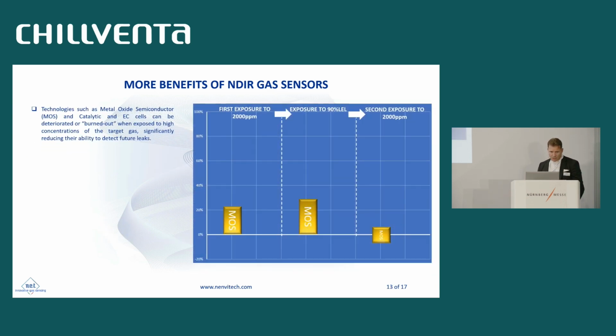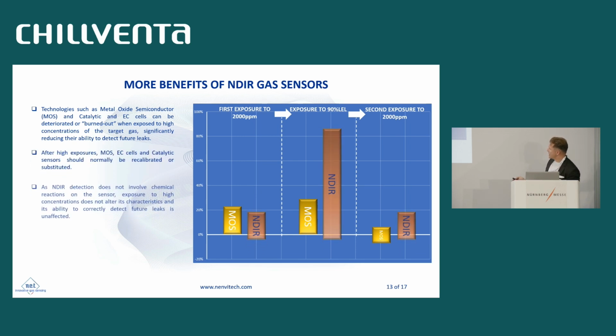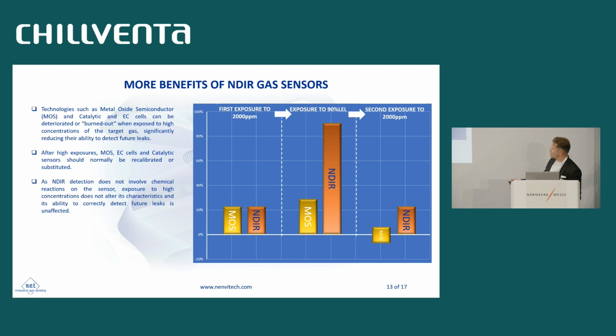Last but not least, immunity to poisoning. Typical technology used in refrigerant leak detection, such as metal oxide semiconductor, can be poisoned or burned out by high exposure to the gas. This is a sketch of a test we made on an MOS sensor as well as an NDIR sensor. Both sensors were exposed to a first level of 2000 ppm. Both sensors reacted correctly. Then the sensors were exposed to 90% LEL, very high exposure. Both sensors reacted, but after that, the MOS sensor got poisoned, the zero has drifted, and a second exposure to 2000 ppm was not detected correctly.